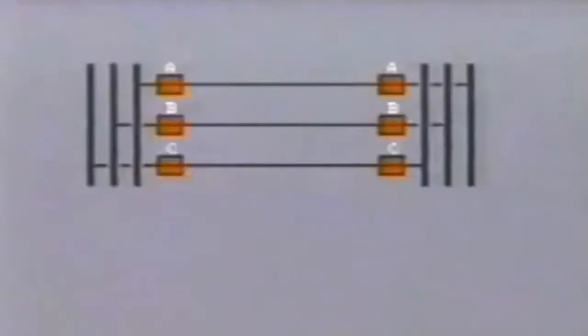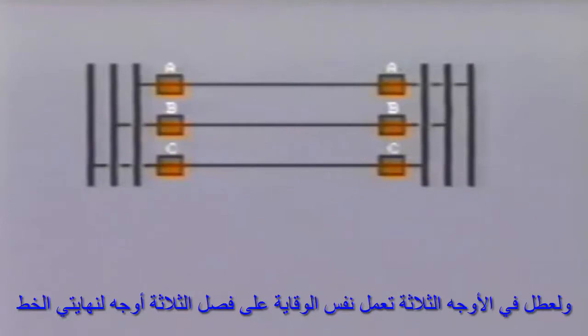Experience shows us that most temporary faults occur on one conductor only, giving us a single phase-to-ground fault. For this reason, many installations choose to trip the faulted phase only. The pilot protection is set up to trip both ends of the line, but on the faulty phase only. For the brief interval of time that this phase is out of service, the remaining two phases will continue to transfer power and so retain synchronism and keep the phase angle difference within a narrow band. The instantaneous reclosing relay will quickly close the breakers again and restore the line to service. Of course, the same protection is set up so that a three-phase fault will trip all three phases at both ends.